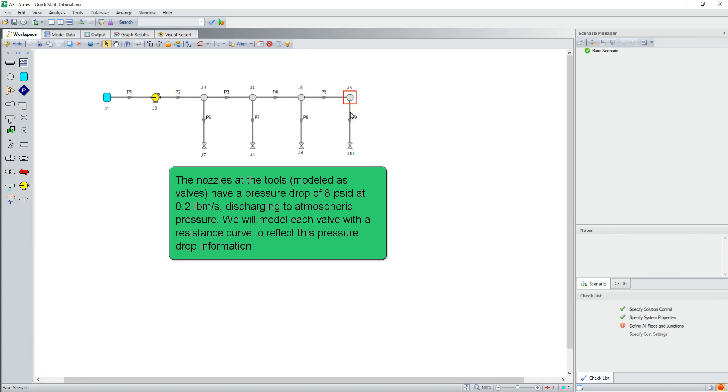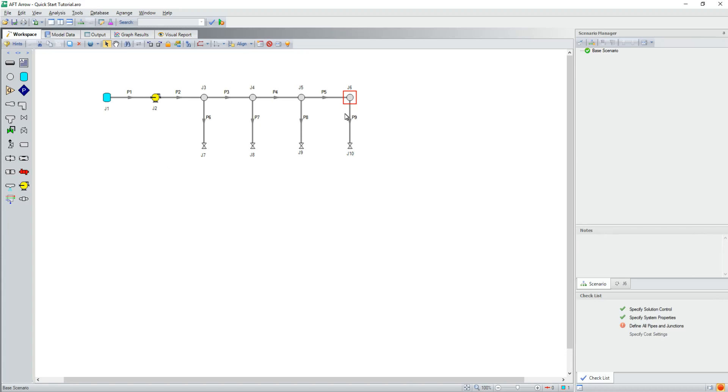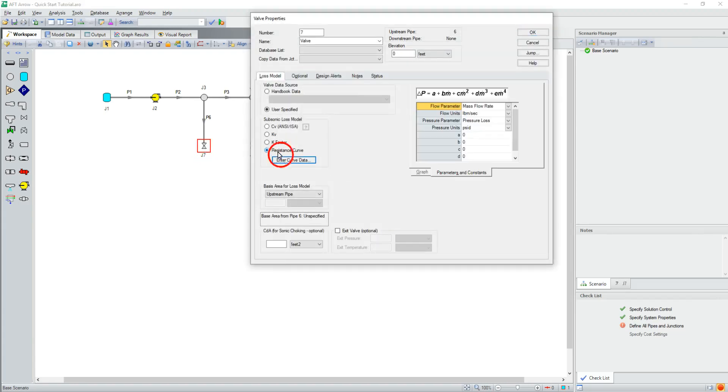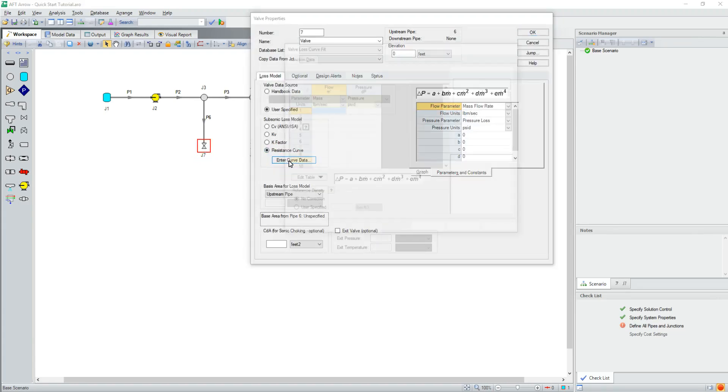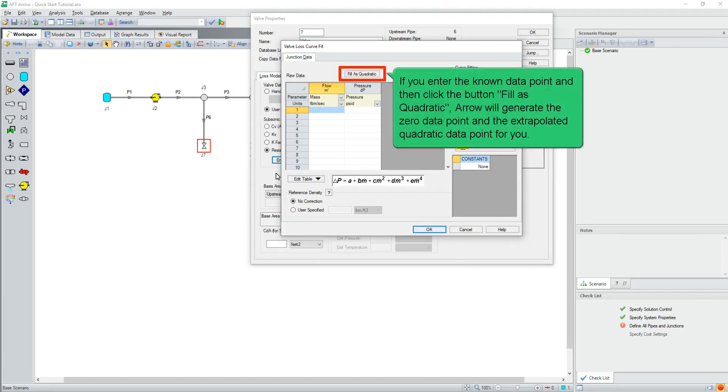As we know only a single data point, we need to make some assumptions. Because pressure drop increases non-linearly, it is usually fairly accurate to use a resistance curve plotted through the zero point, the known data point, and an extrapolated quadratic data point. If you enter the known data point and then click the button Fill as Quadratic, Arrow will generate the zero data point for you.